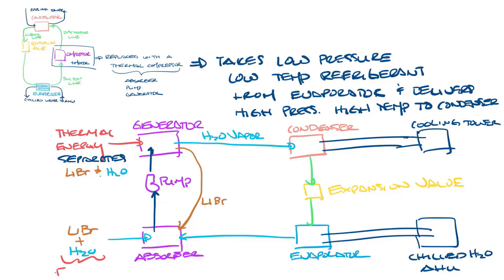The absorption process is exothermic, meaning it generates heat. This heat must be rejected from the absorber to the condenser water and cooling tower loop. Because of this additional heat reject load, absorption chillers require a larger cooling tower compared to a mechanical chiller with the same capacity.